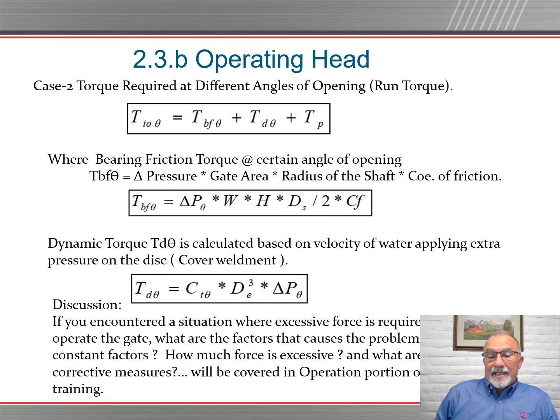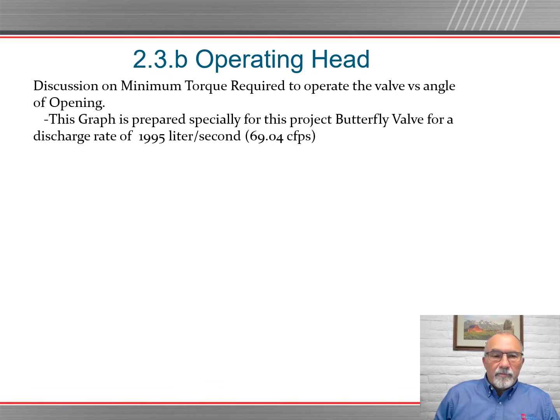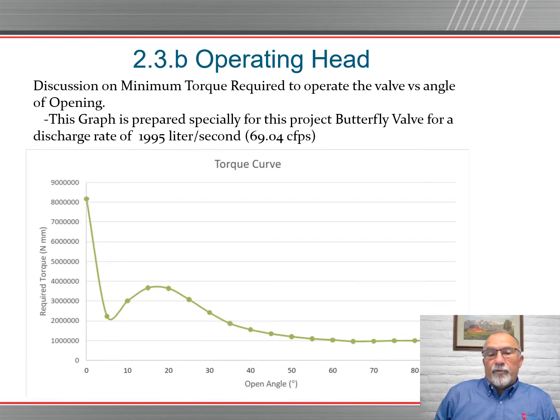How much force is excessive? What are the corrective measures? These will be covered in the operation portion of this training. The operating head discussion is the minimum torque required to operate the valve versus angle of the opening. This graph below is prepared specifically for this project, the butterfly valve for a discharge rate of 1,995 liters per second, or roughly 69 cubic feet per second.